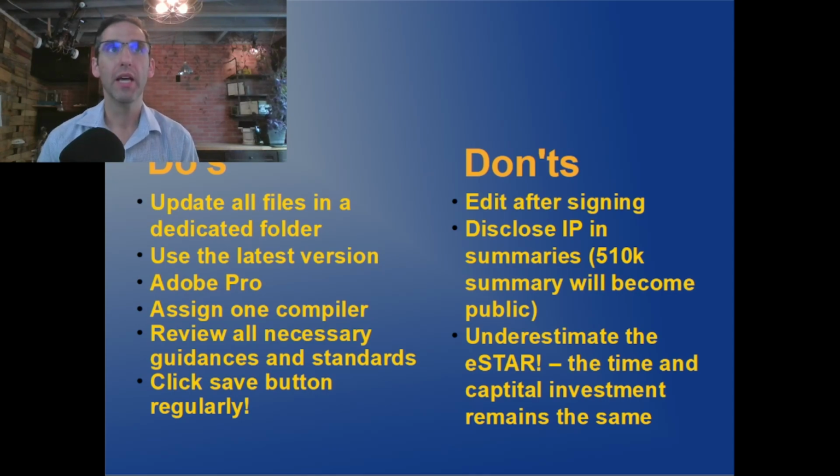This is something that's a big one. There's so many things that just because it doesn't mention it on the eSTAR does mention guidances. It does have excerpts of guidances and standards that's built into the eSTAR, but it doesn't necessarily include everything. It's not totally inclusive of all guidances and standards, but you are responsible to comply with everything.